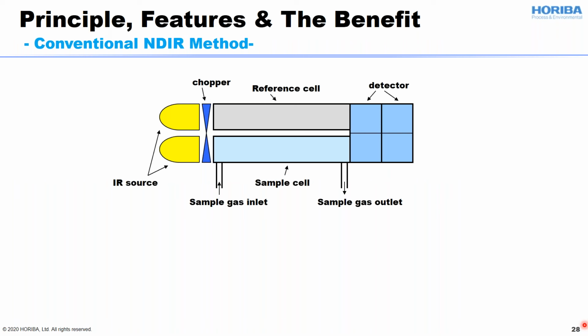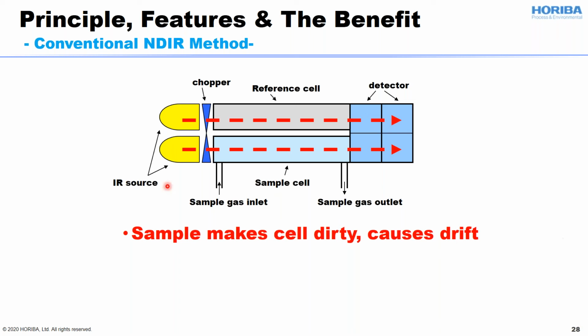This picture is the conventional NDIR method. Basically, it has the light source and the sample cell, two light sources and two light sample cells, and two detectors right here. A sample gas travels from the inlet to the outlet, right? And what you're looking at here is how much reduction could occur while the light is traveling through this path. So the detector on the reference cell is always looking at zero reduction of the power, zero absorption of the light power. And this detector is looking at some absorption because the sample gas will capture the light power.